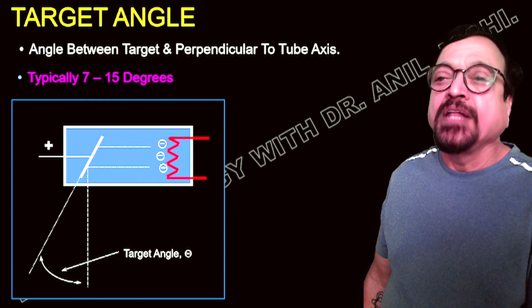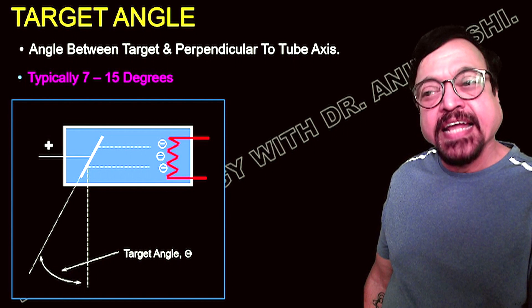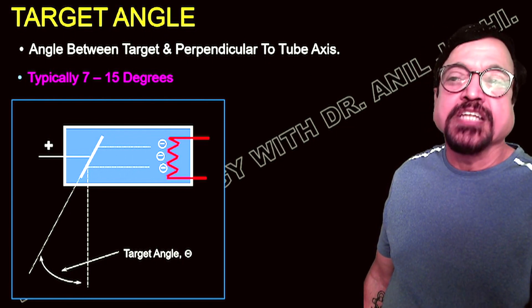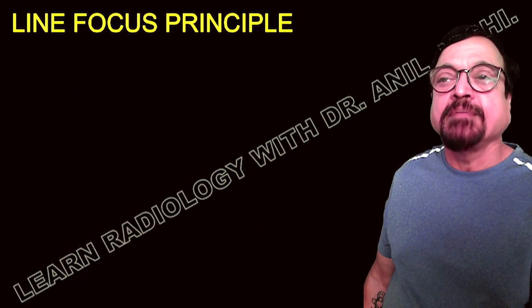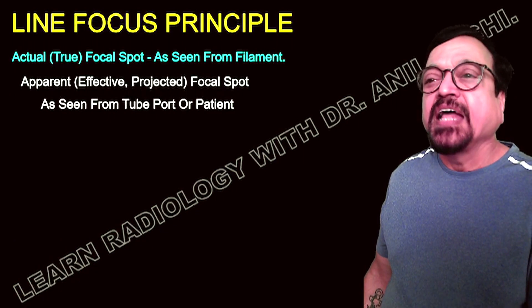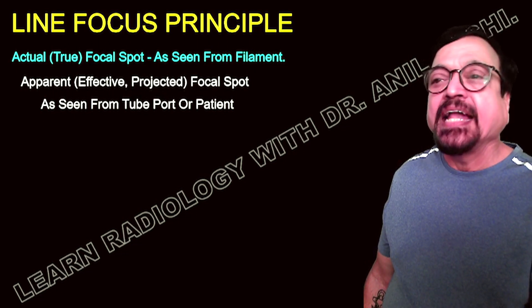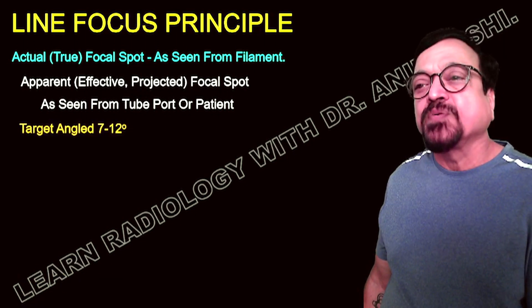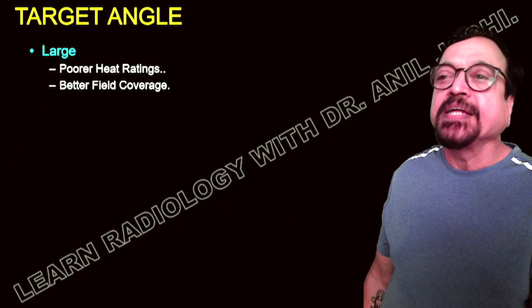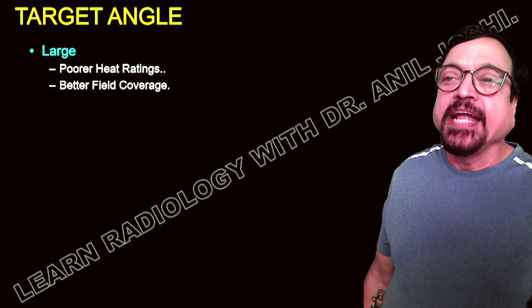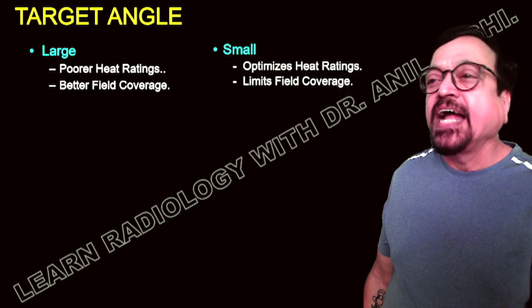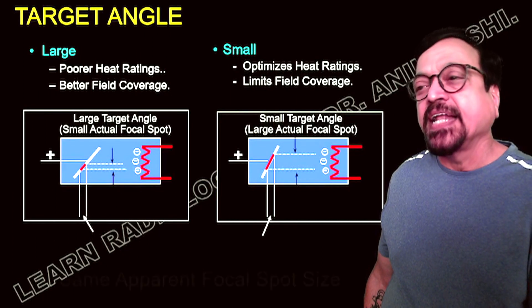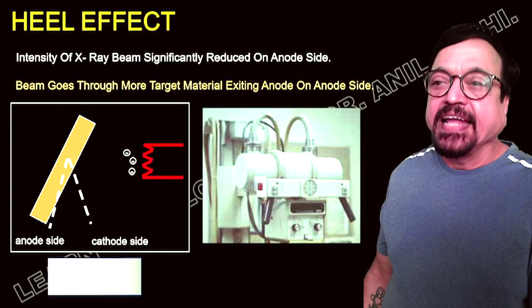The role of the target angle is to focus the x-rays in a particular direction. The electron flow is targeted from cathode to anode, and the anode converts it into x-ray photons. The angle — between 7 to 15 degrees depending on the machine and manufacturer — is essential for directing x-rays. The line focus principle distinguishes the actual (true) focal spot as seen from the filament, and the apparent (effective or projected) focal spot as seen from the tube port or patient. A larger target angle gives poorer heat rating but better field coverage; a smaller target angle optimizes heat rating but limits the field covered.